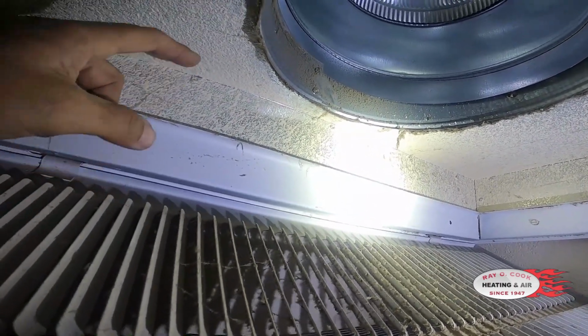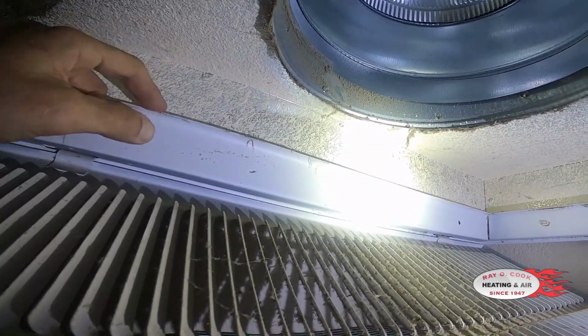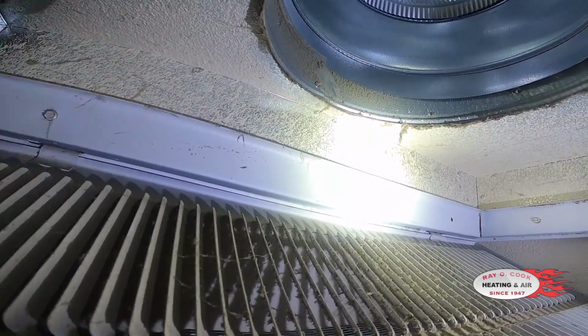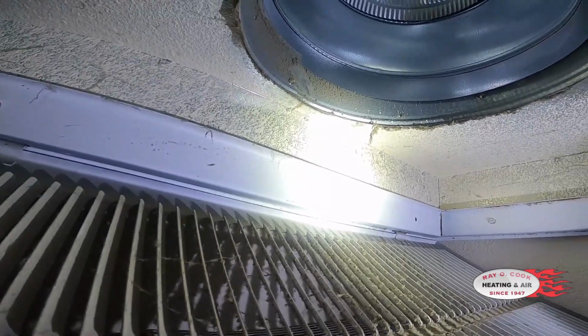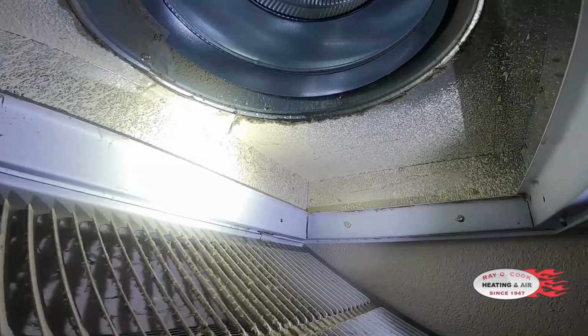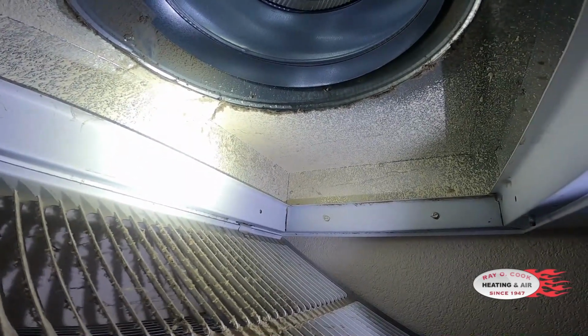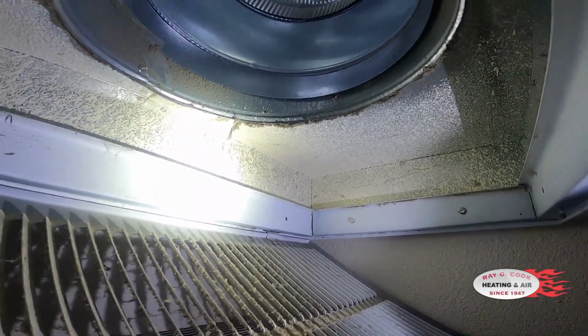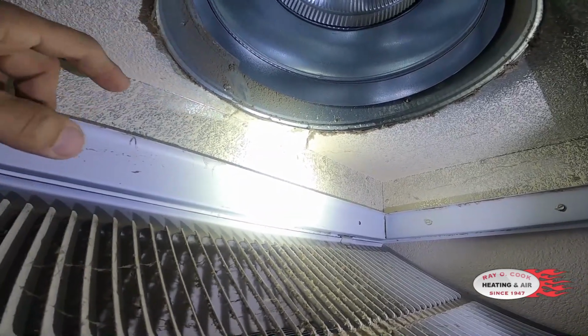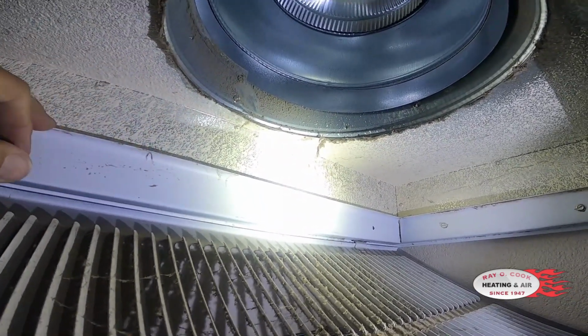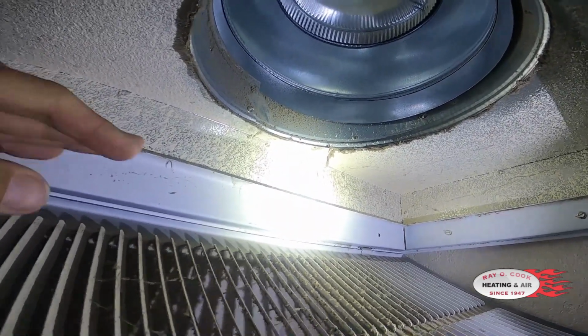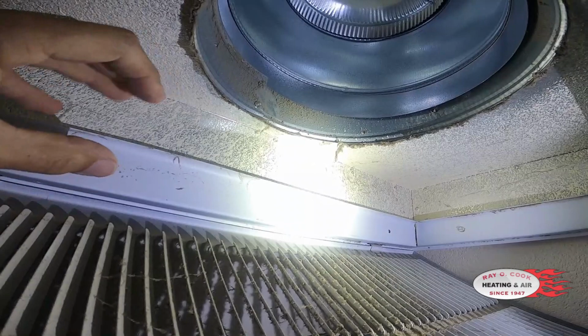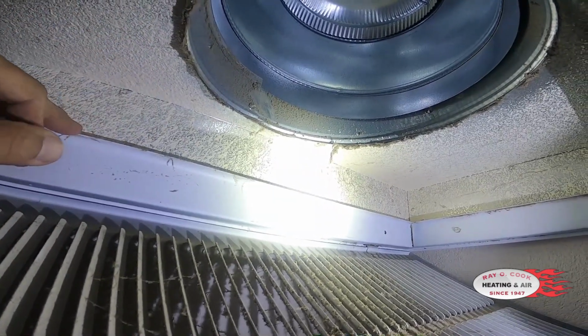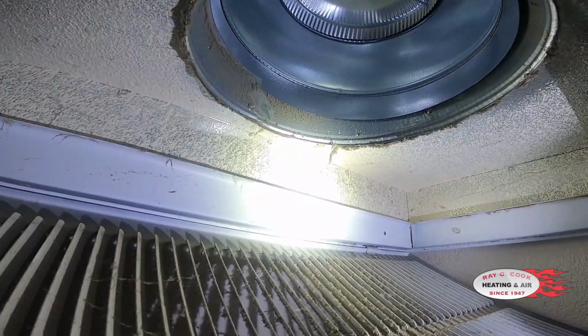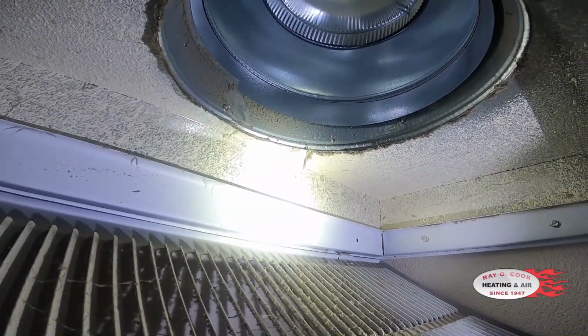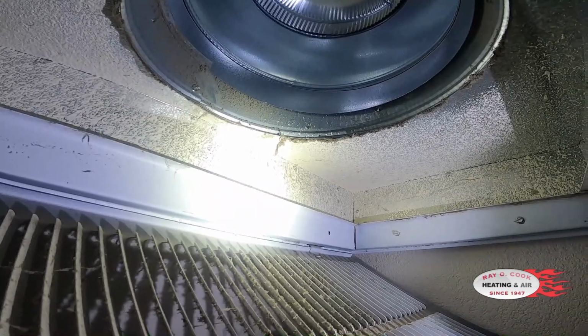You can also see this is a very shallow box, and we'll talk about the shallow box and the more efficient filter here with regards to the 3-inch. But understand that all of this ductwork here that comes off of the unit is above ceiling line. So any leaks or anything we have here is going to allow air from the attic, which is above ceiling line. If we have a lot of restriction here, we're going to suck that air into the airstream, and that's above this filter. So that's where, if we have a real restricted filter here, we can get negative results for sure.